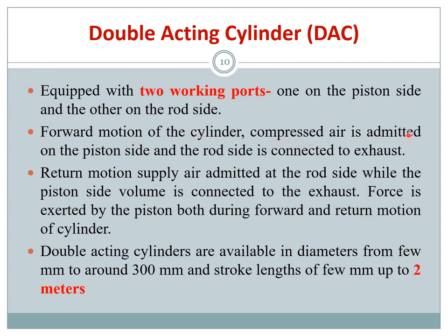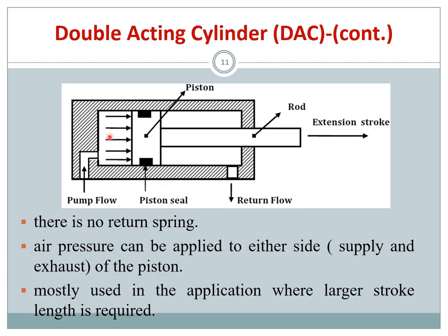For forward motion, compressed air is admitted to the piston side and the rod side is connected to exhaust. There is no spring in a double acting cylinder — so when drawing circuit diagrams, make sure not to draw a spring for a DAC. Air pressure can be applied to either side depending on the desired operation.